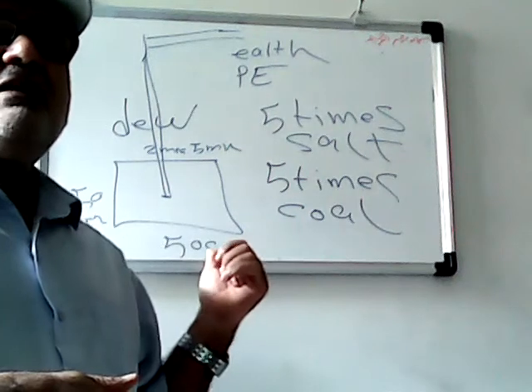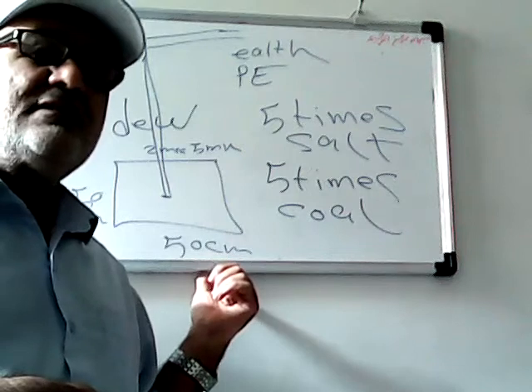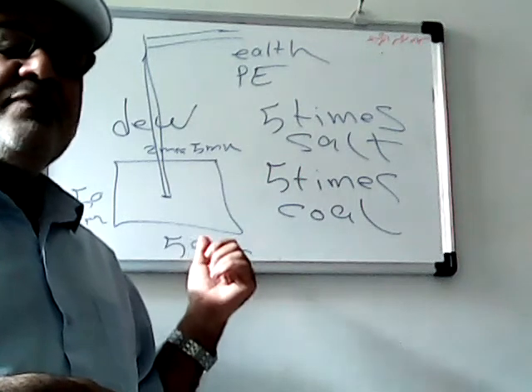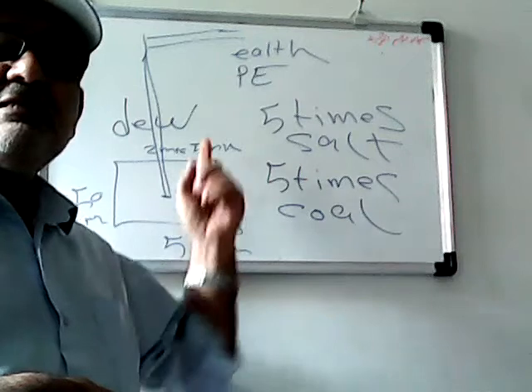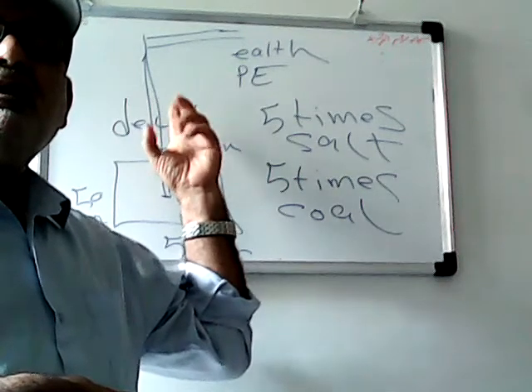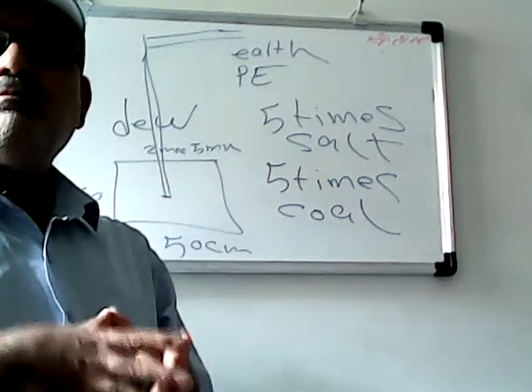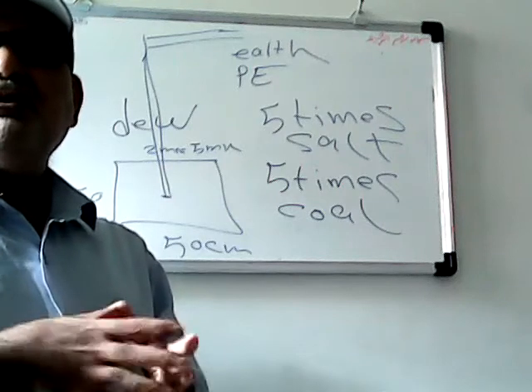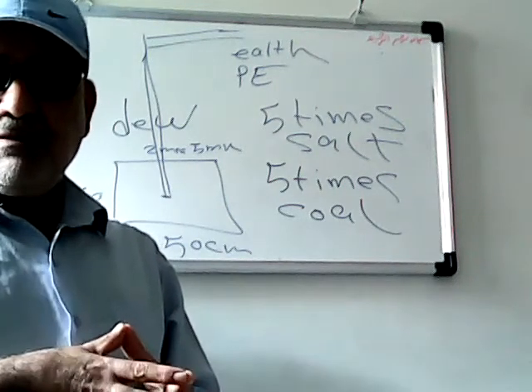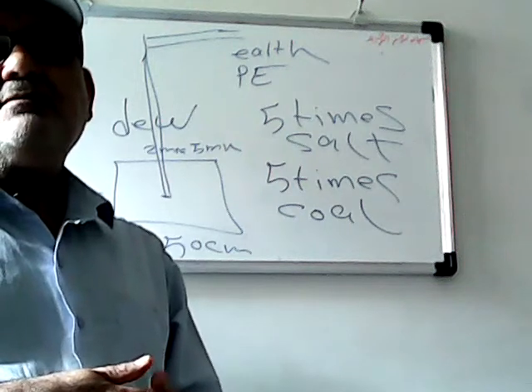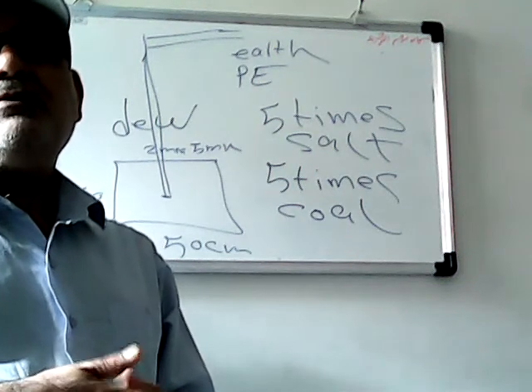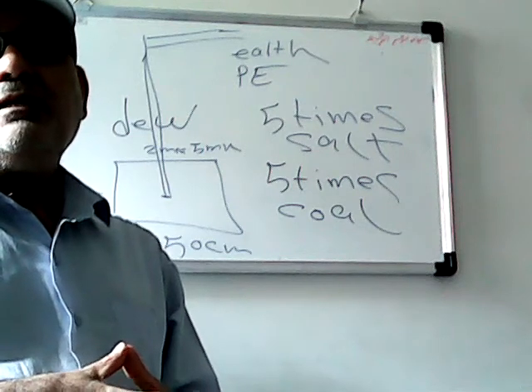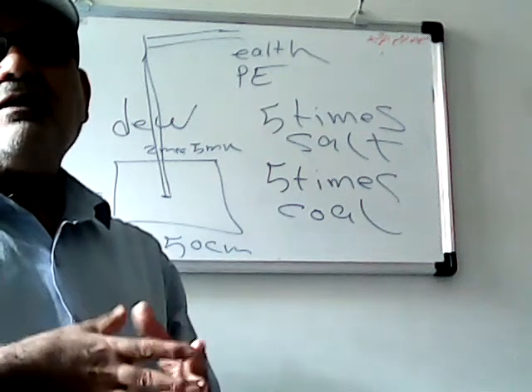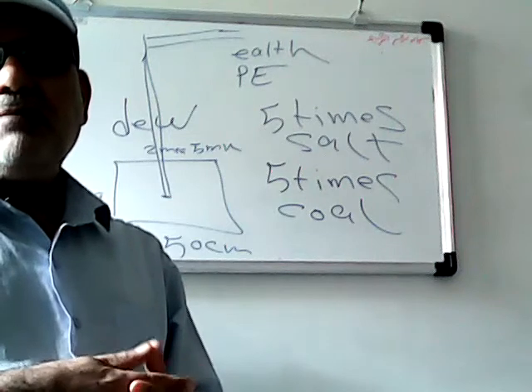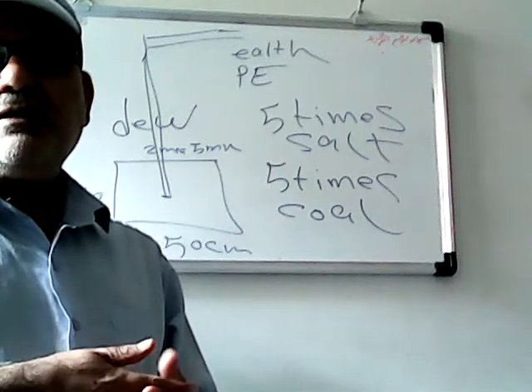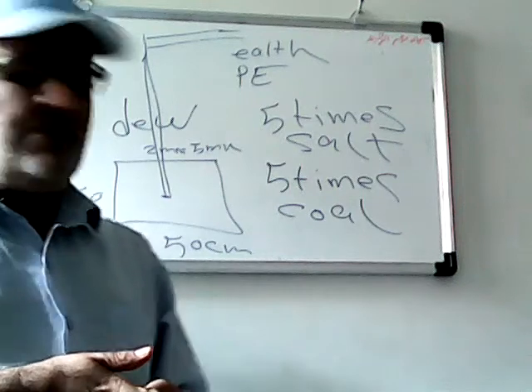That's very important. After the installation, the earth wire and earth pit resistance must be lower - the better. It's between 2 and 5 ohms. This value is recommended by many standards - American, German, and IEC (International Electrotechnical Commission) - as 5 ohms.